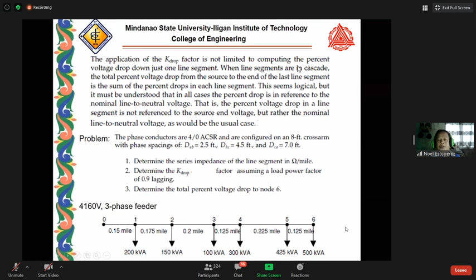Here we have a phase conductor 4/0 ACSR distributed from node 0 to 6. From the upstream going to node 6 at the downstream, we will look at what the voltage drop is when it goes to the last node on the downstream side. So first, with this horizontal spacing, we will determine the series impedance, the K drop, and the total percent voltage drop to node 6.